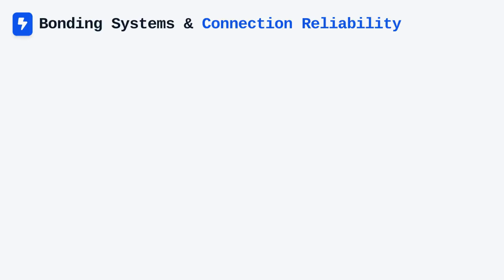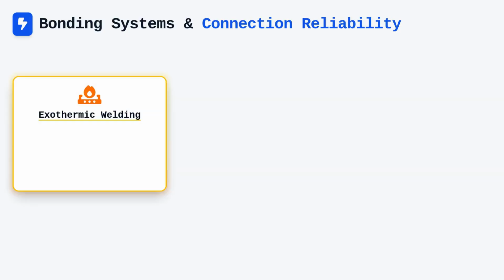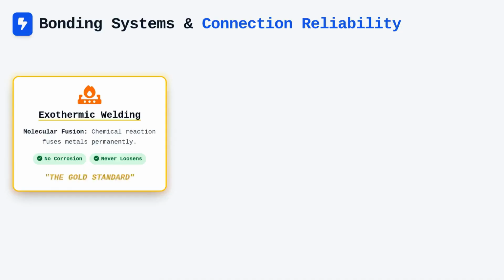When we construct these bonding systems, the quality of our connections determines the long-term reliability of the entire protection scheme. You must prioritize the use of exothermic welding, commonly known by the brand name CAD-weld, for critical connections, particularly those involving the grounding electrode system. An exothermic weld uses a chemical reaction to fuse metal components together at a molecular level, creating a permanent connection that will not loosen or corrode over time.